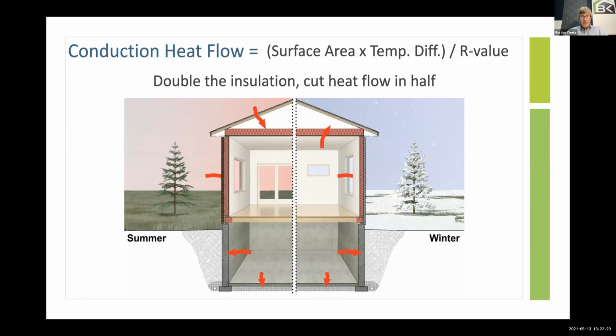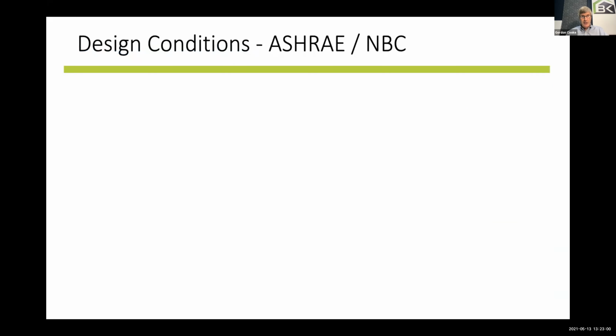Why is that? Well, because the ground is always cooler than the air temperature inside the house, right? The deep ground temperature, 4 foot deep, is roughly 50 degrees. Again, we have to stay in Fahrenheit, 55 degrees. So we actually get a cooling effect out of the ground. It reduces our heat gain. It reduces the size of our air conditioner to not insulate the slab. So you can imagine in the south, I was just doing a heat loss, heat gain for the south, and under slab insulation helped us in winter, hurt us in summer. And the further south you go, the more you would say, no sense insulating under the slab, because that's actually increasing my cooling load. So get a little sense of that, if you will.